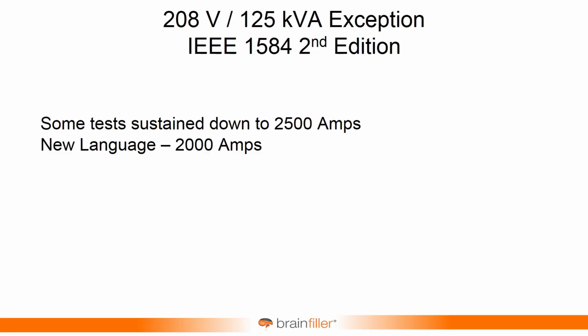There was a lot more research with the barrier tests and with lower currents and lower voltages. And what we found was that the 125 kVA exception, it's not really an exception, but that's how people refer to it, is a little bit optimistic. After extensive testing for the next edition of IEEE 1584, the new language simply states that sustainable arcs are possible, but are less likely in three-phase systems operating at 240 volts nominal or less with an available short circuit current below 2,000 amps. So the way it stands right now, with the next edition of IEEE 1584, the 125 kVA exception is gone. And in its place is a reference to 2,000 amps, and still a possibility of sustaining, but not as likely.